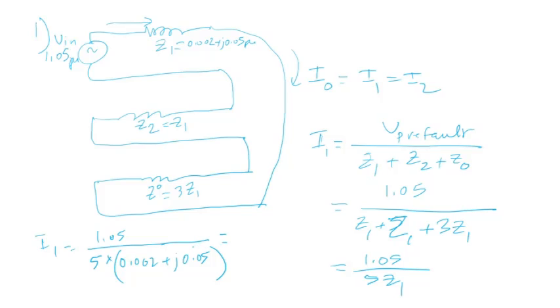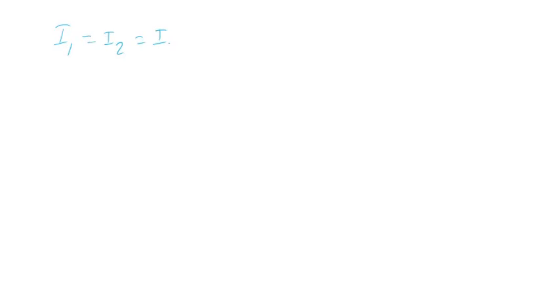For a line to ground fault, I0 = I1 = I2. The sequence current I1 equals the pre-fault voltage divided by Z1 + Z2 + Z0. Since Z2 = Z1 and Z0 = 3×Z1, the denominator is 5×Z1. So I1 = 1.05 / (5 × (0.002 + j0.05)) per unit. Converting the impedance to polar form: 0.05004 at an angle of 87.7°. Carrying out the calculation gives I1 = 4.1966 per unit.